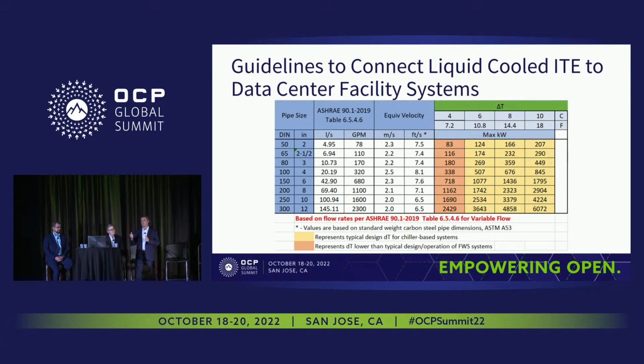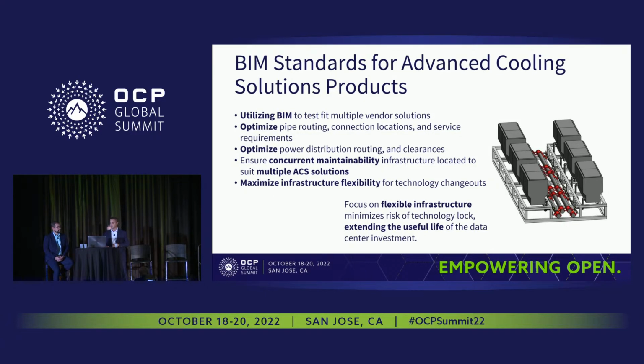It basically takes energy standard recognized limits for pipe flow rates and velocities, correlating them to FWS delta T's, to give folks a quick glance: if my pipe size is this and my FWS delta T is this, how much capacity could I theoretically support at that set of connections? These attributes are integrated into the system design.